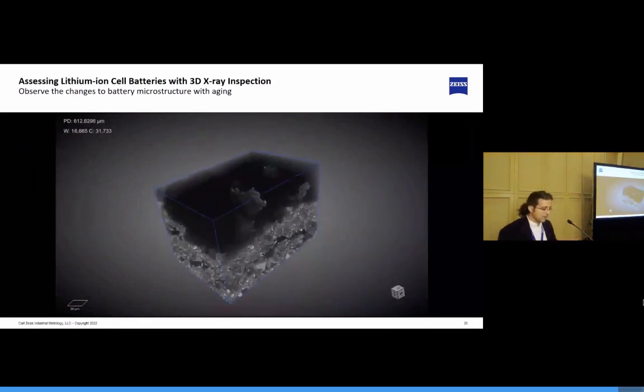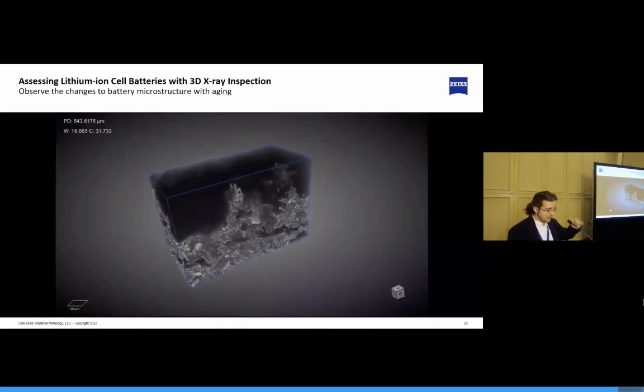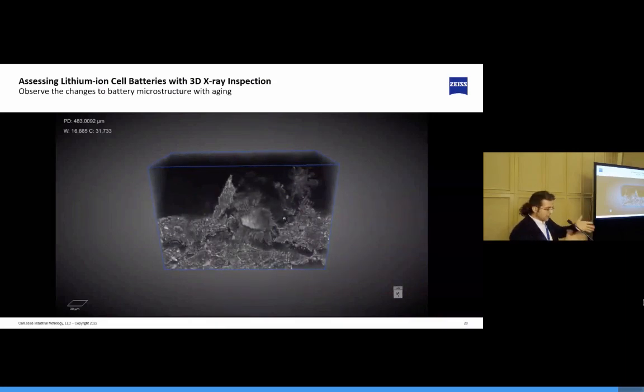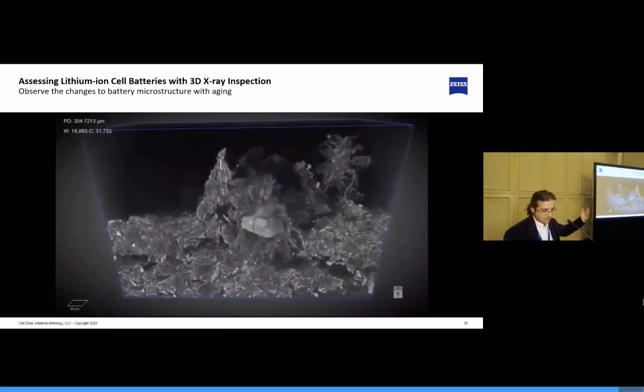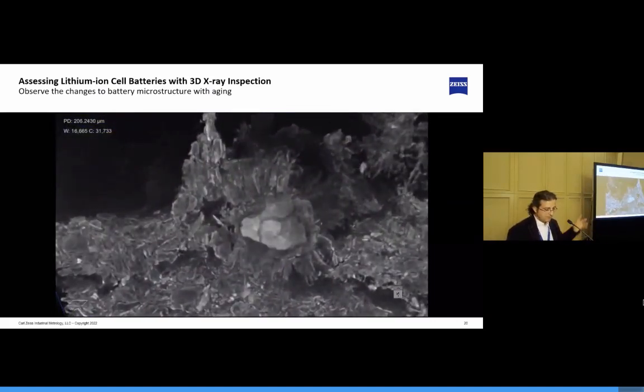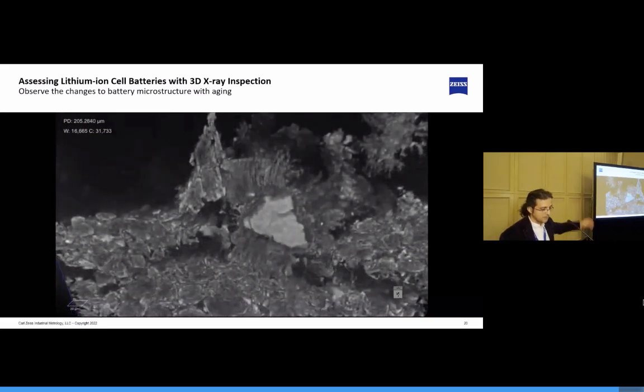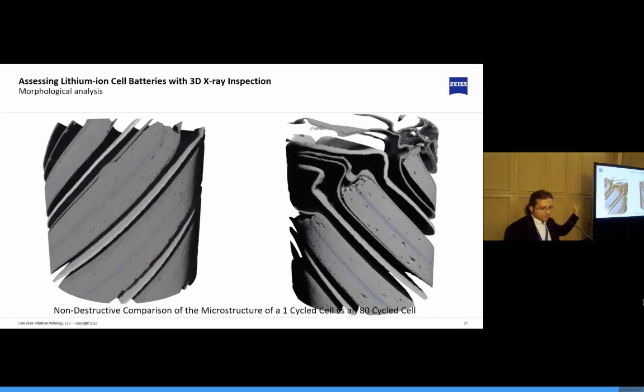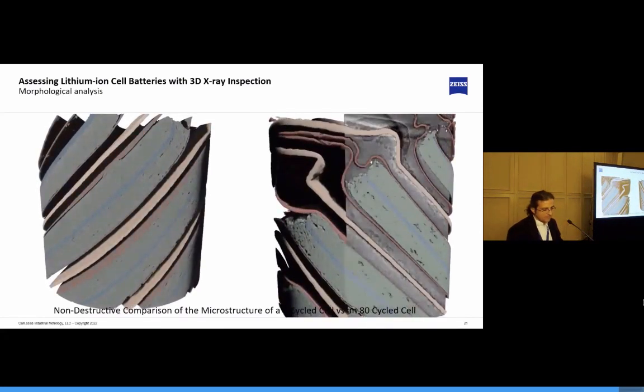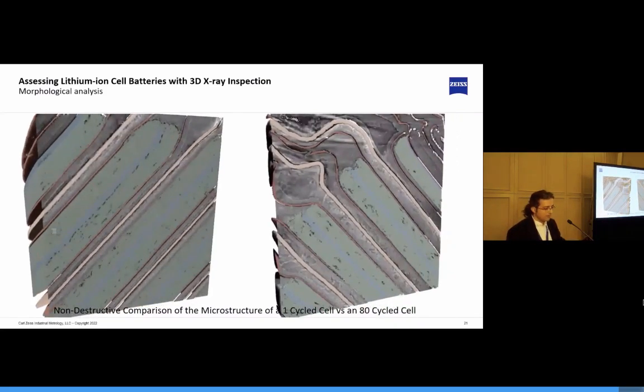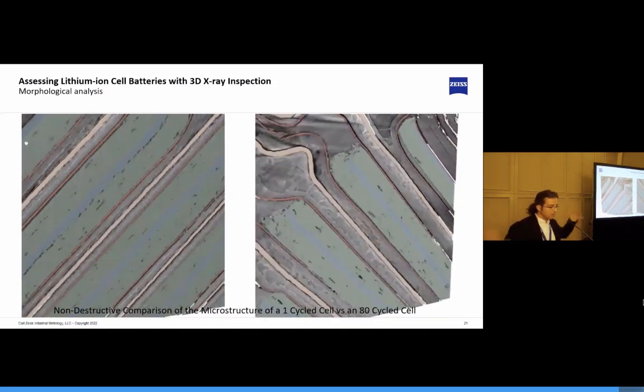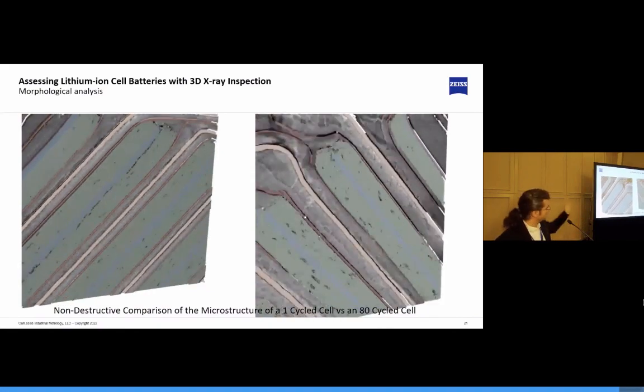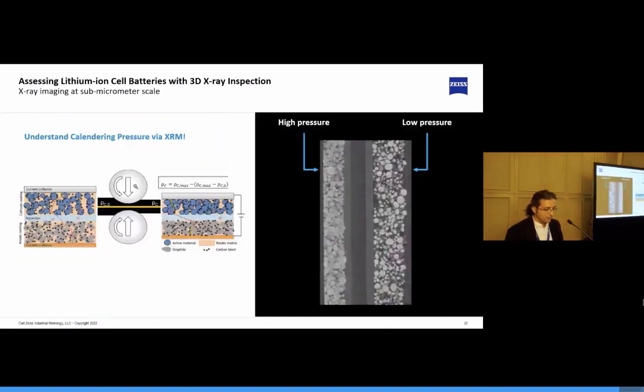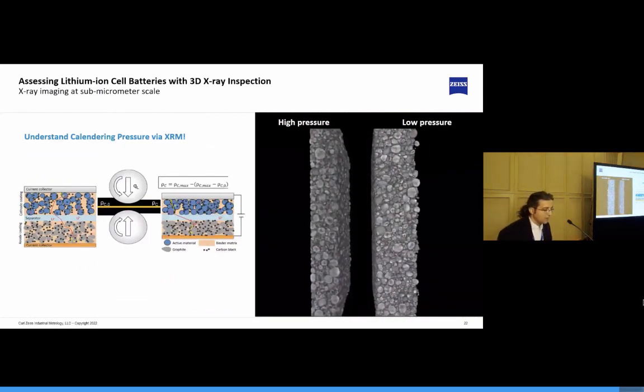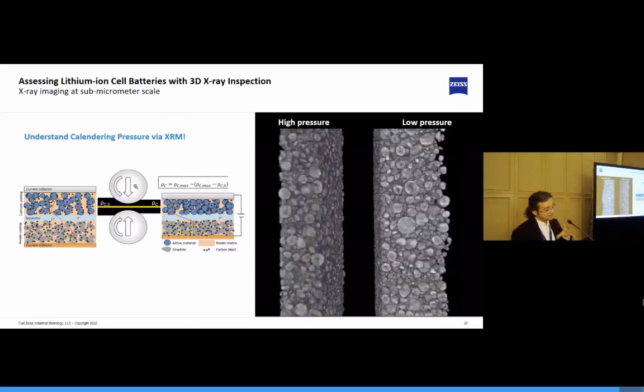Now, if you want to go to higher resolution, there are some limitations on size. If you go to nanotomography, in which you have to slice a portion of the battery, you're still doing non-destructive imaging of that portion. You don't have to slice phase by phase. And in this case, you can see what is happening in the same example, but in 3D. You can do other types of studies. It's not only about aging. Well, certainly aging, but you can see some morphological deformation in the edges of the electrodes, stress formation, some variation of the radial distance, and separation of the different interlayers of the battery, which is certainly very important for you. And we can also check the outcome of poor mixing and a weak battery compaction process.